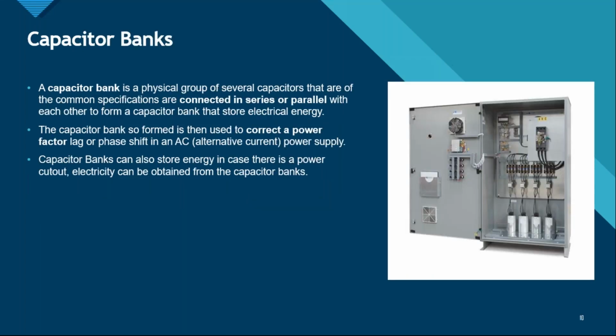Then there can be capacitor banks, basically a panel with huge cells, you can say. A capacitor bank is a physical group of several capacitors that are of the common specifications, are connected in series or parallel with each other to form a capacitor bank that can store electrical energy. The capacitor bank so formed is then used to correct a power factor lag or phase shift in an AC power supply, right? To rectify power factor, to keep the power factor close to 1, right? So that it helps in the electrical supply.